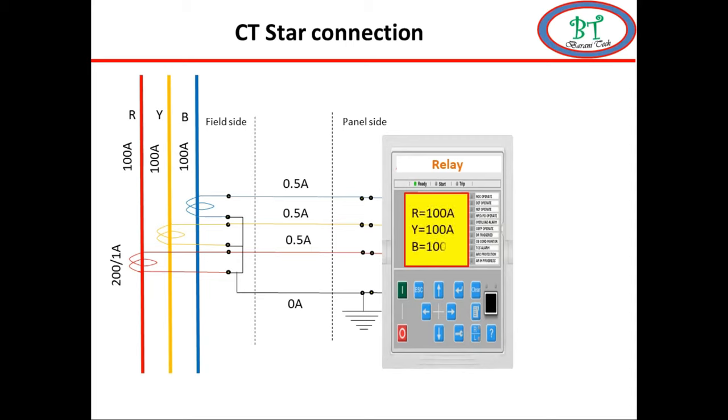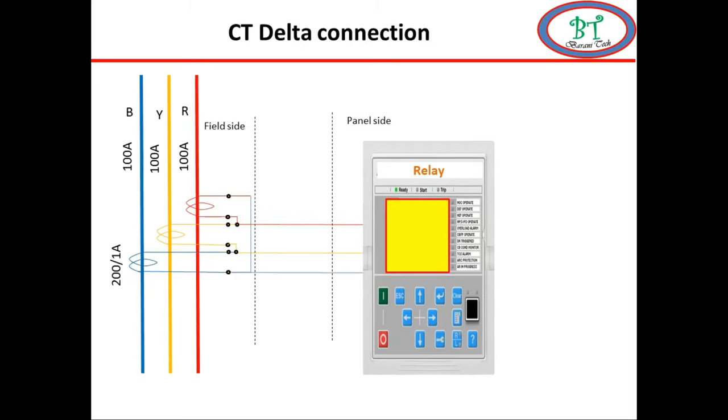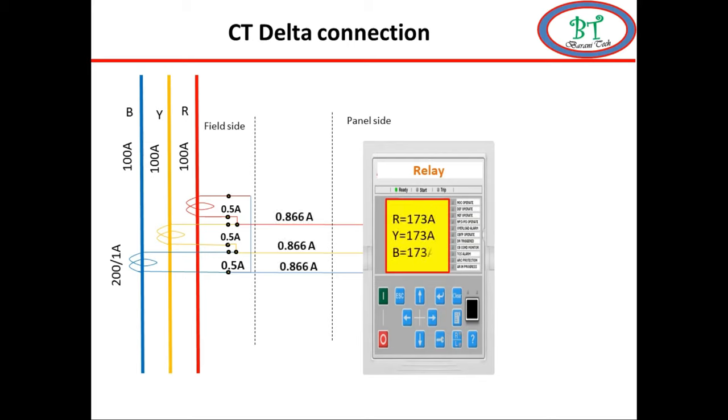Now we will see the delta CT secondary connection. As per the line current of the system and CT ratio, the CT secondary current will produce. Since the CT secondary is delta, it will reflect the phase current of the system. So we have to calculate the phase current to match the line current.